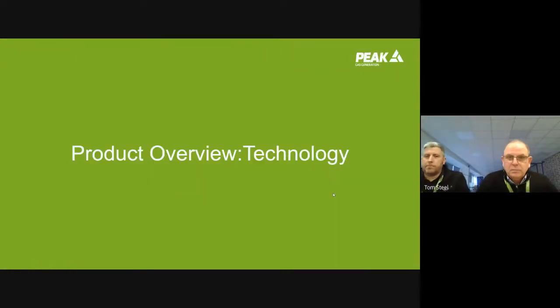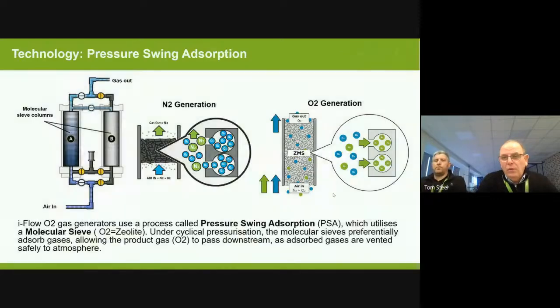So let's have an overview of the technology. Obviously, you guys have been working with oxygen concentrators. So really the technology from the zeolite side doesn't change. We are going to use a PSA system, where one tank is pressurized, and that's going to adsorb the nitrogen, and the other tank is going to be depressurized, so we flush any of the nitrogen out to atmosphere.